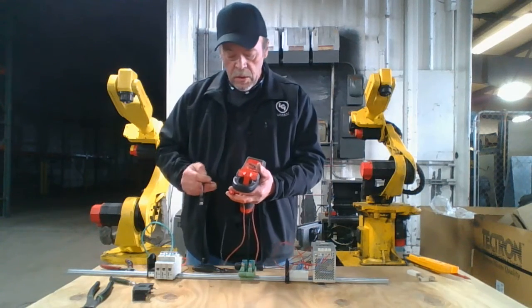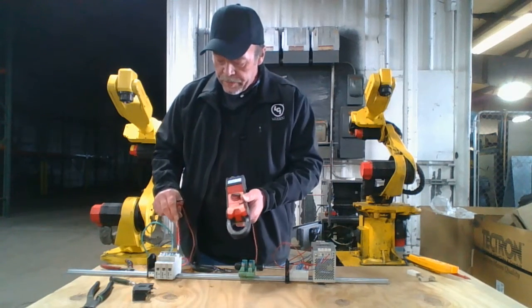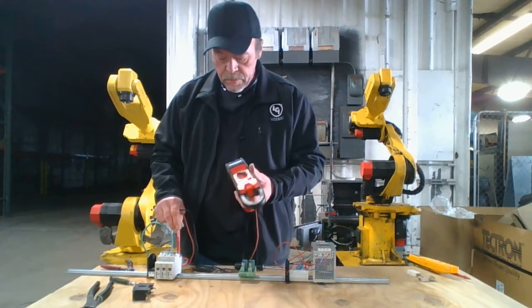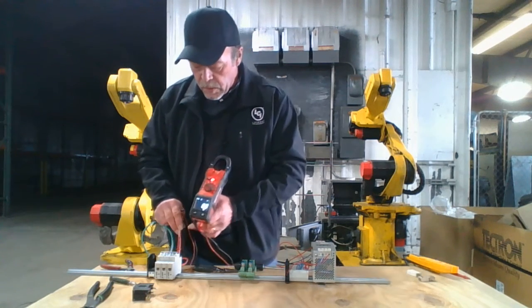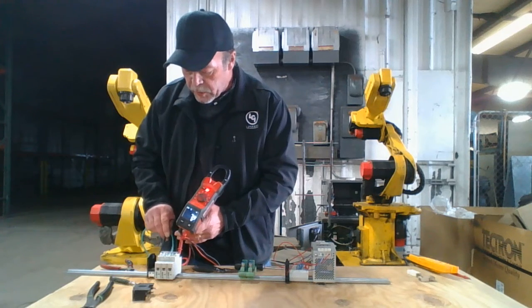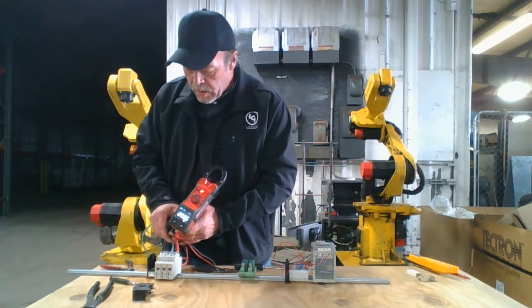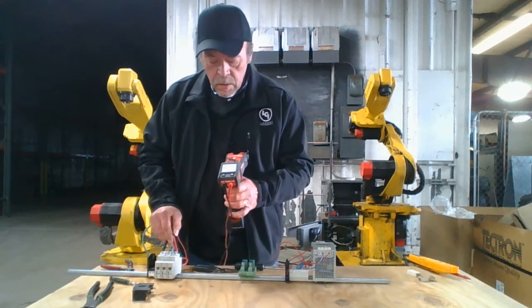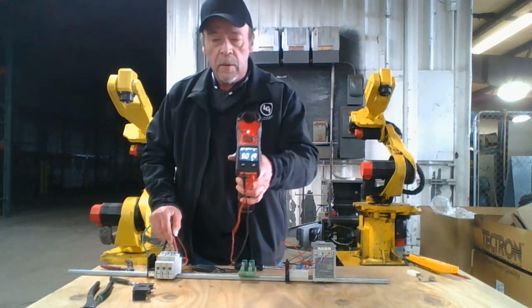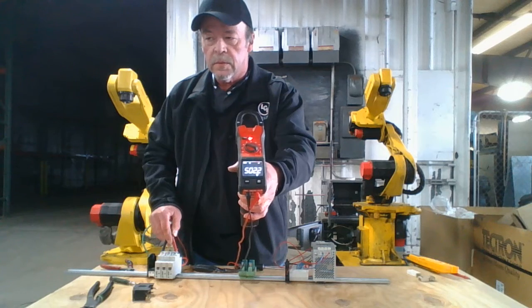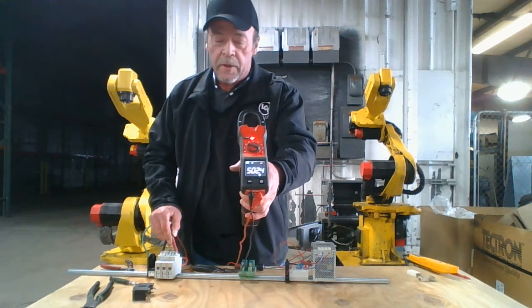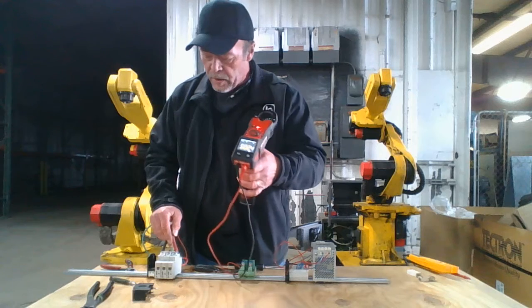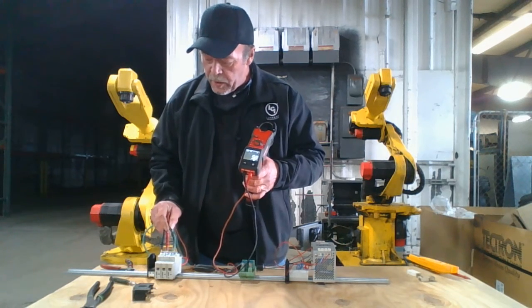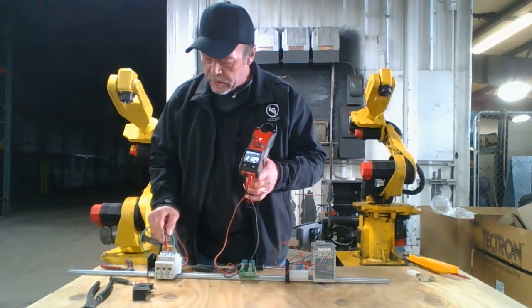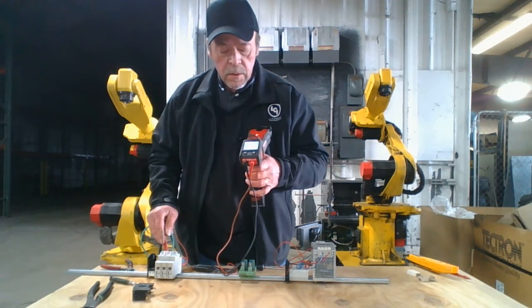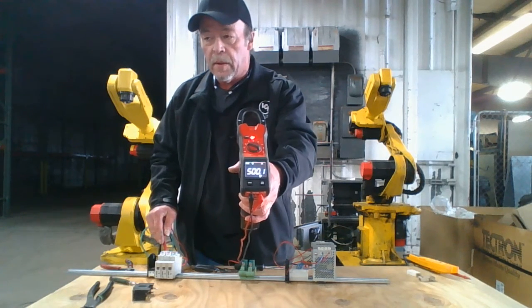So when I check my power, to ground, I'm running 502 volts. It's pretty high. It's supposed to be 480. And then I checked, that was L1. I checked L3 to ground. And again, I am at 500 volts.